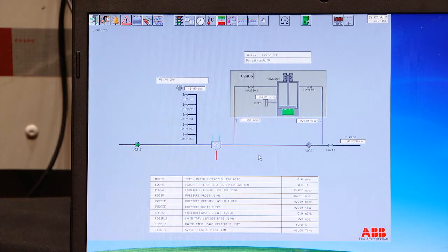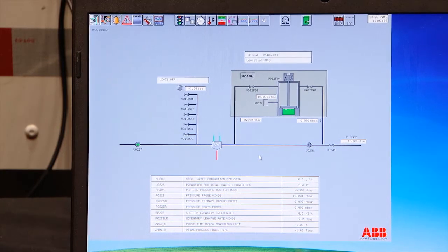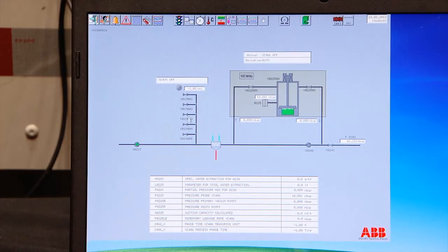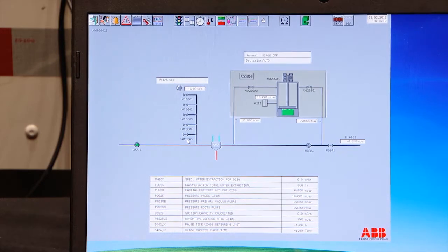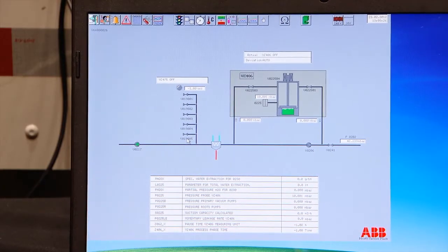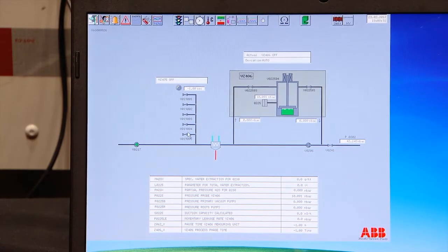And this is the device that we hooked up over the roots pump. Now we have turned off the roots pump. We have connected the VZ475. We'll take the readings for that pressure curve to see if we can match it to the actual one. You don't have to compare it. We have the calibrated values. We know the values for the leakage value. What this one does is we have a calibrated leakage. We are assuming that the system is vacuum tight, and then we open a valve here, and then we know how much leakage this one is generating.